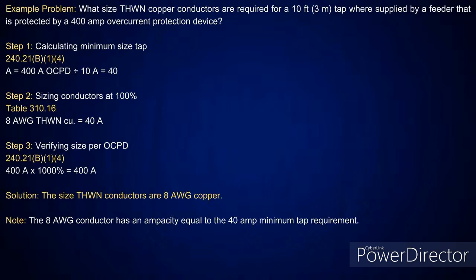But the thing here is, remember this about taps. If the tap is 10 foot or less, you divide by 10. All other taps above 10 foot, you take at a third. The only difference is if I'm doing a tap and I have a transformer within that tap, then you have to get, on the secondary side, the ratio of the transformer. The interesting thing is all other taps over 10 foot, you take at a third. Even when that transformer is in that tap, the primary is taken at a third and the secondary is taken at a third. The only difference is you have the ratio of the transformer on the secondary side. Okay? So let's take a look.